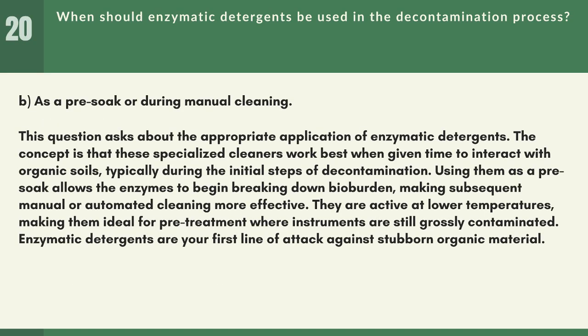Answer: B. As a pre-soak or during manual cleaning. This question asks about the appropriate application of enzymatic detergents. The concept is that these specialized cleaners work best when given time to interact with organic soils, typically during the initial steps of decontamination. Using them as a pre-soak allows the enzymes to begin breaking down bioburden, making subsequent manual or automated cleaning more effective.